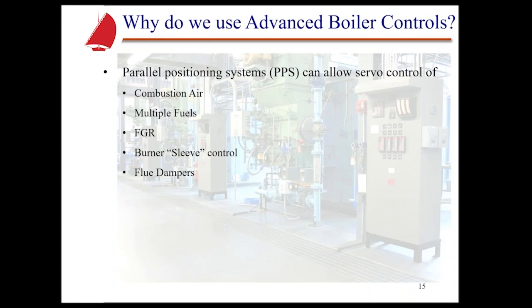I've actually had technicians tell me over the years, well, I've changed out air servos about every 6 months. And it's like, well, why are you doing that? Something's going on. Something's not set up properly. Something's not aligned properly. Is there a heat issue? Maybe that needs to be looked at. Is there a vibration issue here? If so, that needs to be addressed. Vibration and heat can really kill the servo quicker and shorten its life, so you need to be very aware of how they're operating.